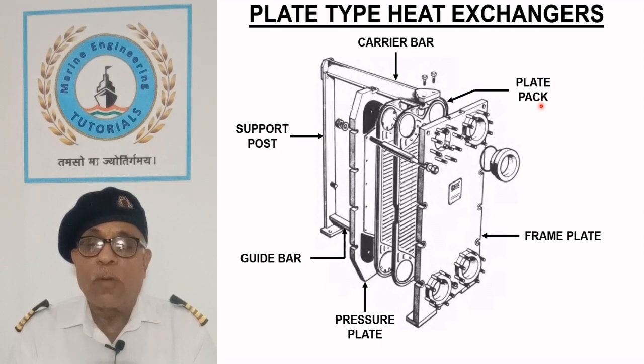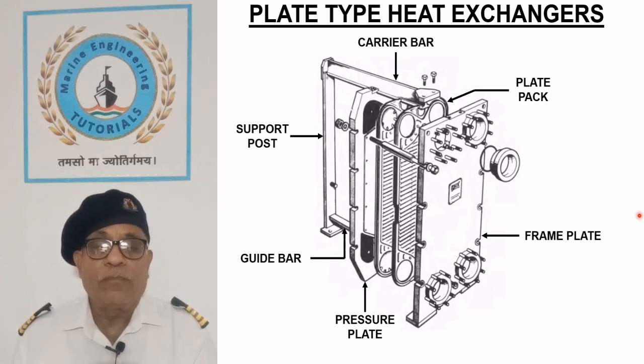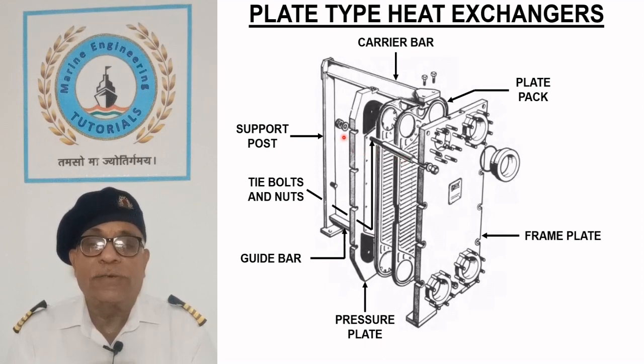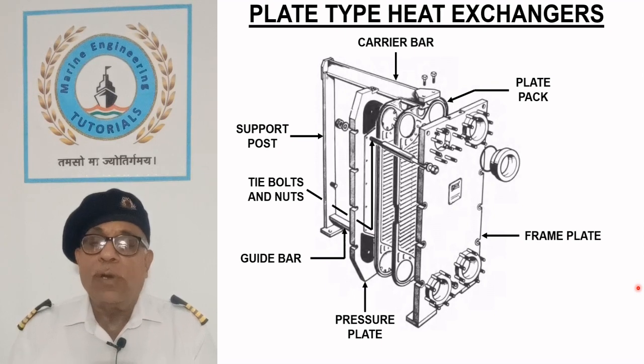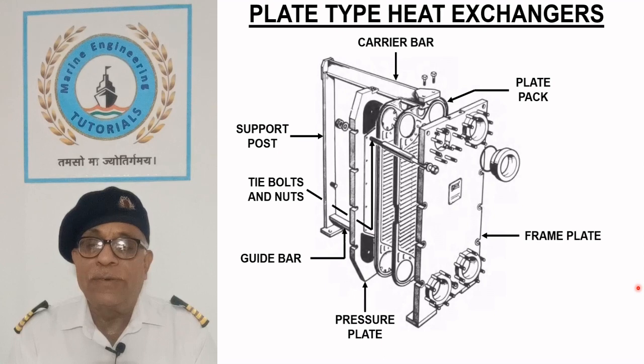They are made from identical metal pressings with horizontal or chevron pattern corrugations, each with a nitrile rubber joint. A number of tie bolts and nuts keep the plates pressed up to prevent internal leakage between the liquids or external liquid leakage to the surroundings. The joints are squeezed when the plates are assembled and clamping bolts are tightened. Over tightening can cause damage to the plates, thus, the correct procedure should be followed. A torque wrench should be used for tightening and the correct stack length should be obtained after tightening.